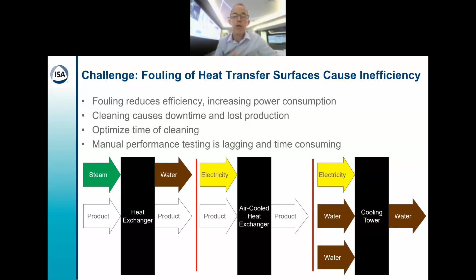A performance monitoring system includes a software piece plus automatic data collection using add-in sensors to understand what's going on inside the equipment. Once the inefficiency is detected, as indicated by the fouling factor, you can do something about it. You can determine the optimum time for cleaning to restore efficiency, to minimize energy loss, while also minimizing the impact of scheduled downtime or from capacity reduction. From the software, you can pinpoint the fouling to a specific bundle of a heat exchanger bank.